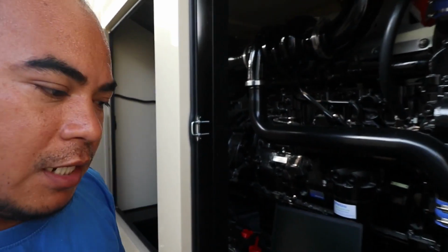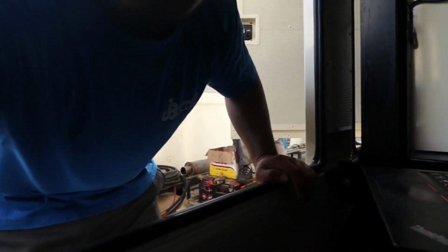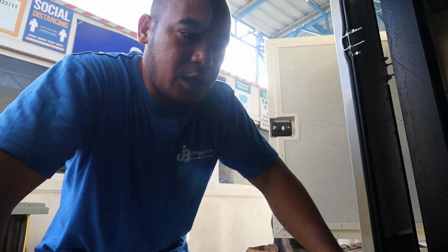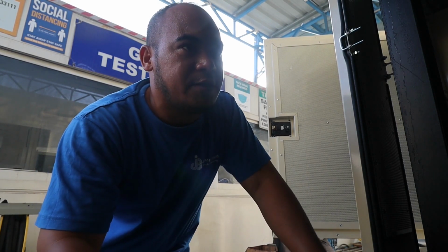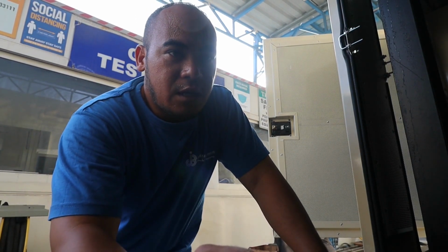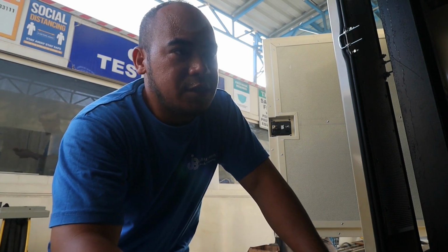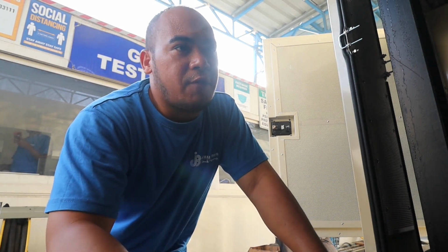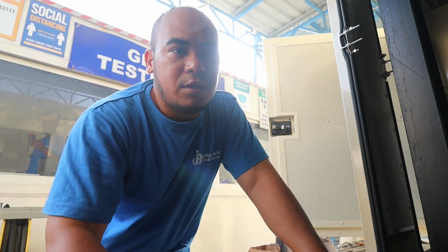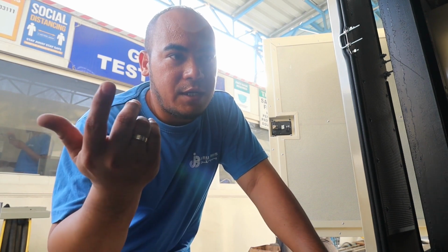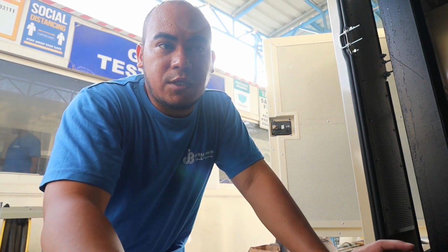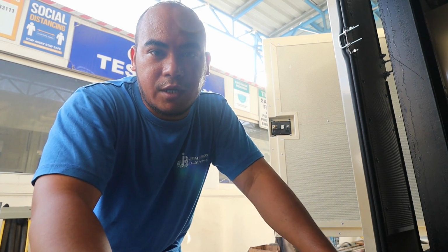So in the configurations for our ECM, you can select the communications, and you can select 3 items there: 5 VDC, CAN bus, and PWM. Since we're using CAN, you have to activate that one. If you have a PWM like the MTU, you can use that also. And the other one is the 0 to 5 volt, like in the Deep Sea, we are using that one, in order to have the command for your speed biasing.